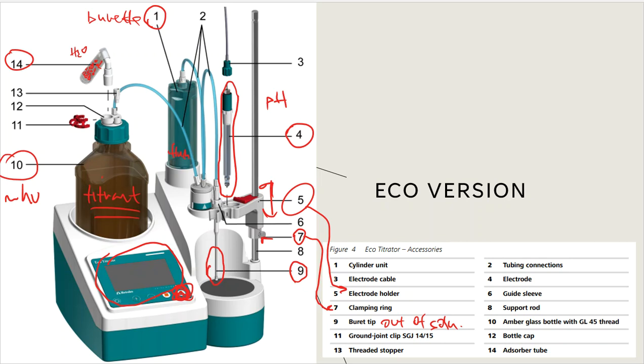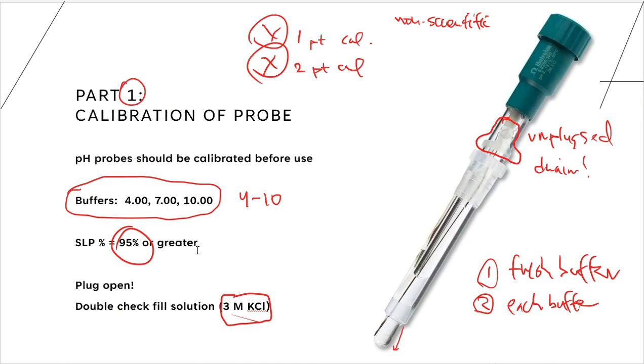And then after it gets finished with the second, it's going to say, raise the probe, clean the probe, put it into your next buffer, and then hit enter. Okay, so when it's finished, you accept it, and then you clean it off, you put it into the next buffer, and then you hit enter or whatever button it tells you on the screen, and then it will finish out that third buffer, and then it will automatically calculate the slope, ta-da, percent that you should be getting from the probe or what it saw from the probe. And hopefully, cross our fingers, it's 95% or greater.